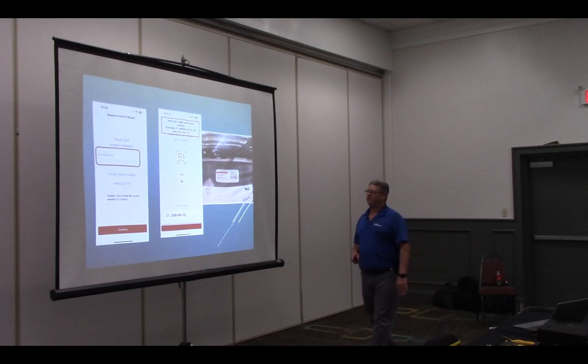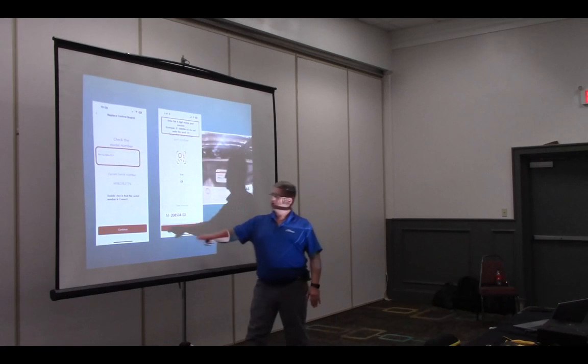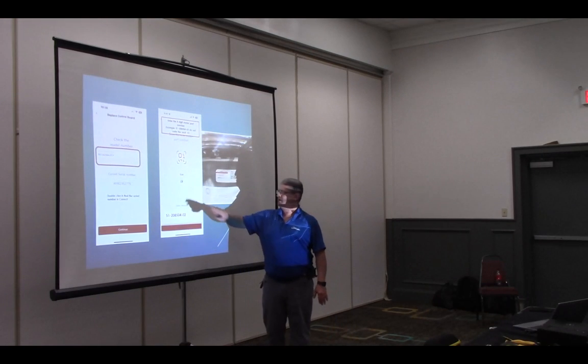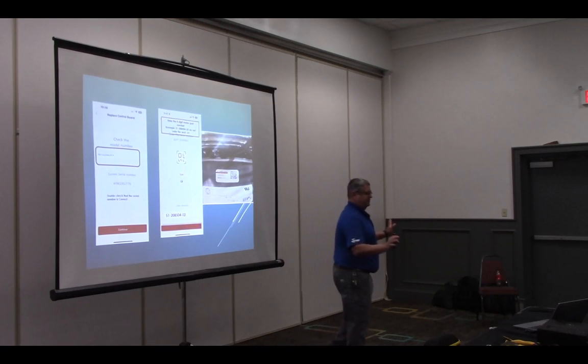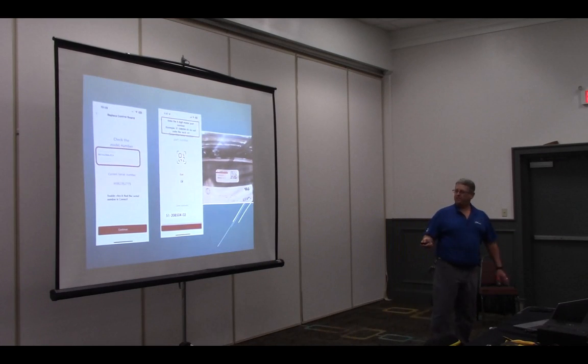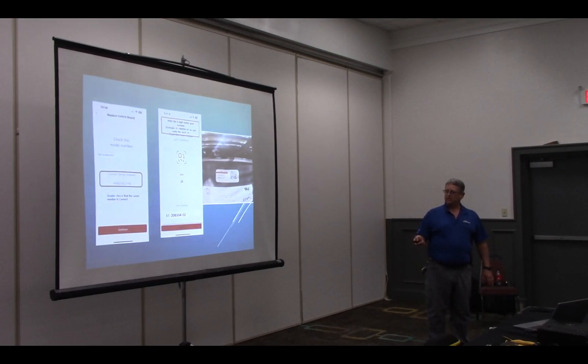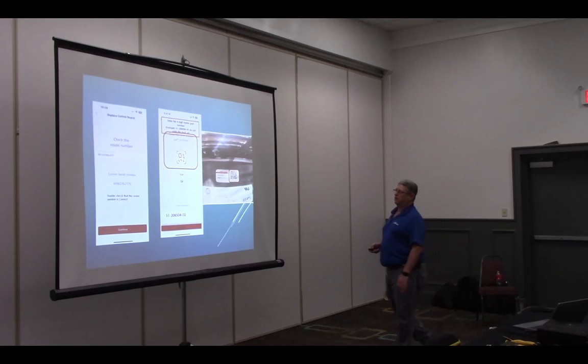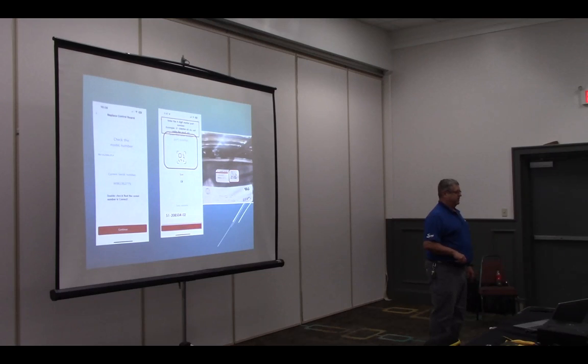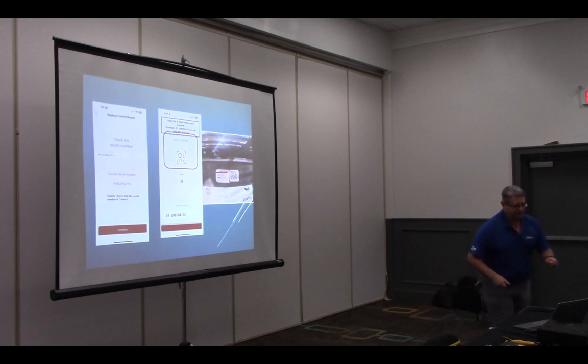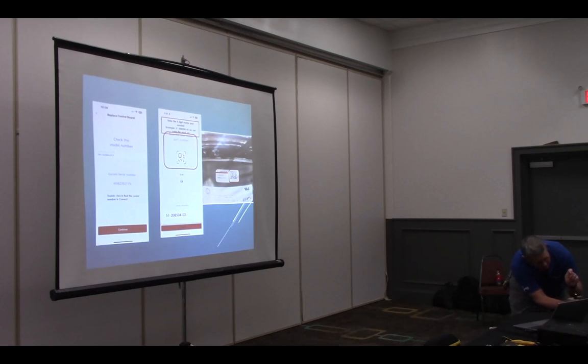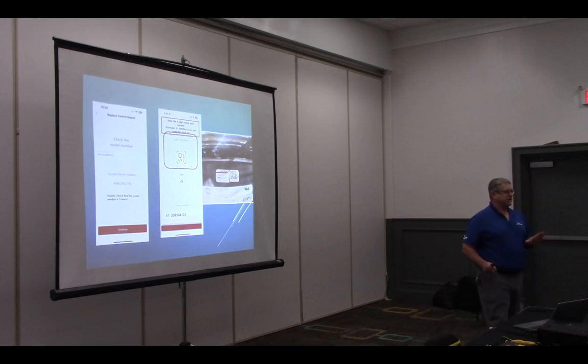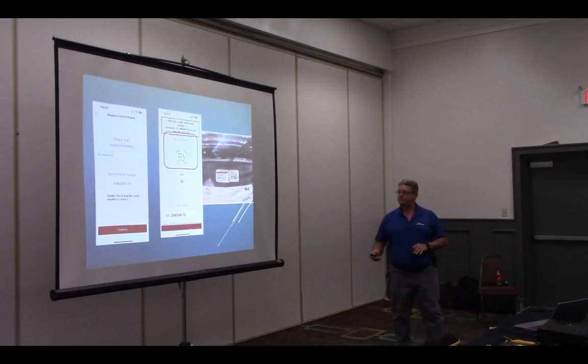If you have an Apple phone, this screen is going to come up first. If you have an Android, this screen comes up. I don't know why it does it differently. It just does. But if you have an Apple, it's going to ask you to verify the model and serial number of the unit. Come down here, verify, and click continue. Then you come to here, it tells you to scan the motor part number or enter it manually. I'm going to tell you now, don't try scanning it, it's a pain. You've got to undo all 4 screws, get down here, raise it up, get your arms up under there, get your phone in there. It's just hard. Just enter it manually, that is the easiest way to do it.